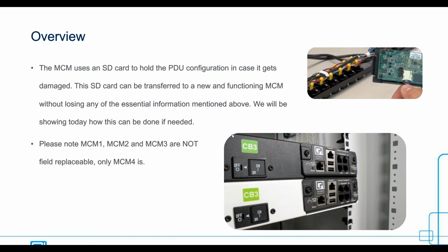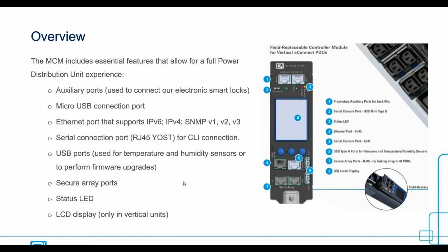Our legacy PDUs will have MCM1s, MCM2s, MCM3s. Our newer eConnect PDUs will have MCM4s, which are the only ones that are field replaceable. To confirm which one you have, look for where it says eConnect Controller 4 at the top of the field replaceable MCM. The main controller module is also designed to manage many of our essential eConnect PDU features.